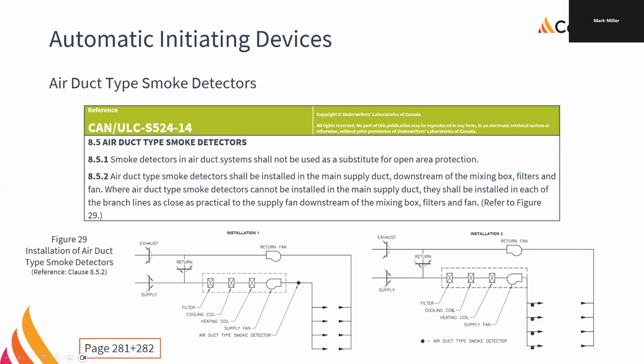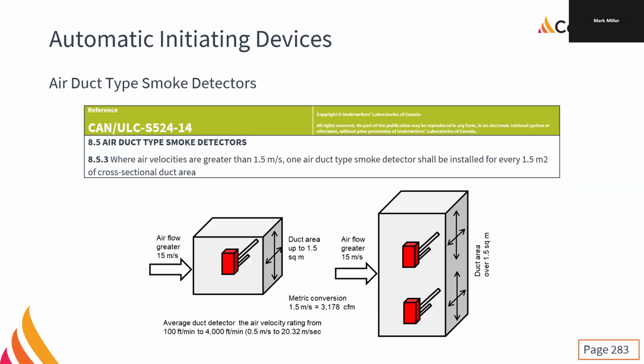So we have to make sure that we have our correct coverage. And then if we have high airflow, we need to put in more because the air is just traveling by too fast to be able to pick it up. And if we have very large ductwork, we have to put in more because we can only cover so much area, right? If we're at air velocity greater than 1.5 meters per second, we have to install a duct smoke for every meter and a half squared of cross-sectional duct area. Usually this isn't an issue. Most buildings, they've gone towards smaller air handling units and more of them, so you can have more detailed control.